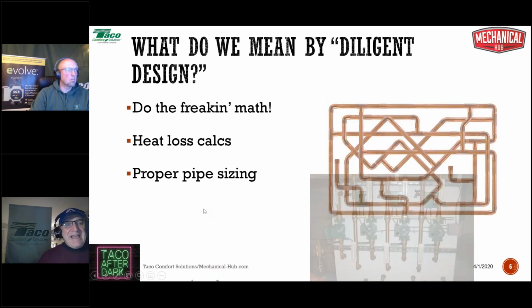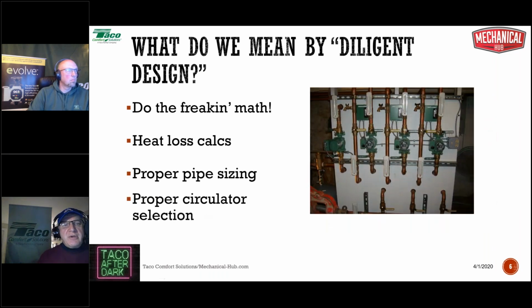That's all math. And knowing all of this, knowing the heating load and sizing the pipe properly, gang, then and only then can we get down to the serious business of selecting the circulator properly. And no, my friends, there's no such thing as one circulator being the only one you'll ever need because it has three speeds. That's a fairy tale. And no, there's no such thing as just stick a variable speed circulator on it, push the button, it'll figure it out. That's another fairy tale. It doesn't work that way.